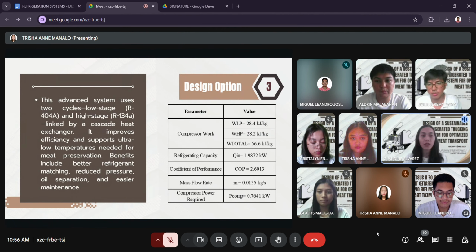Design option 3, the two-stage vapor compression cycle with heat exchanger. This advanced system uses two cycles, a low stage using R404A and a high stage using R134A, linked by a cascade heat exchanger. It improves efficiency and supports the ultra-low temperatures needed for meat preservation. Benefits include better refrigerant matching, reduced pressure, oil separation, and easier maintenance.